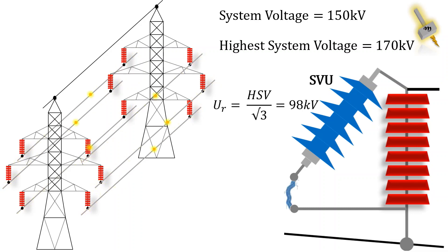Now let's see an example. Let's take a system voltage of 150 KV. It will have a highest system voltage of 170 KV. So the rated voltage of the SVU will be 98 KV.